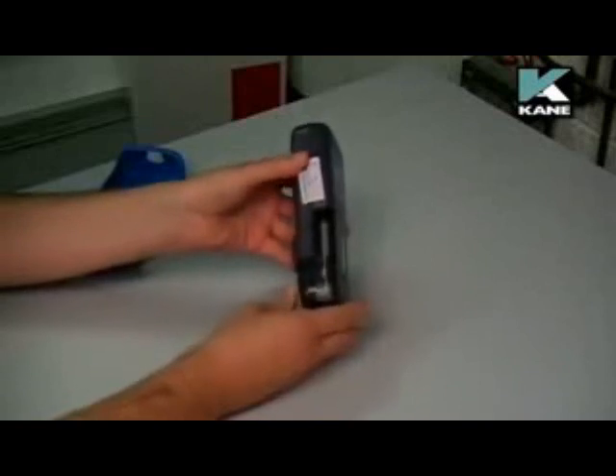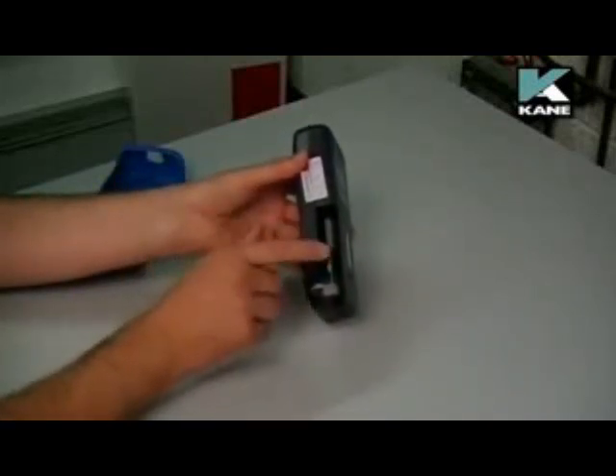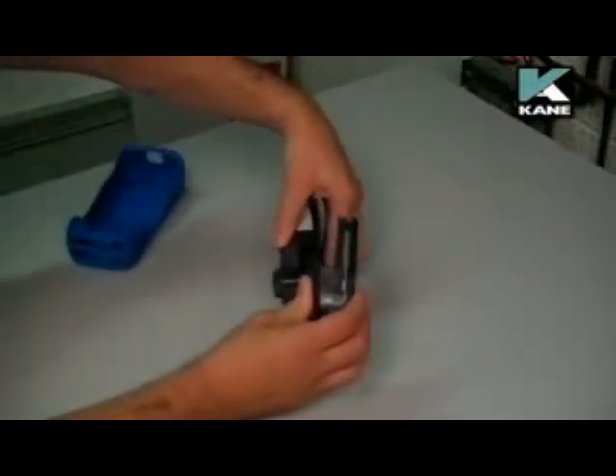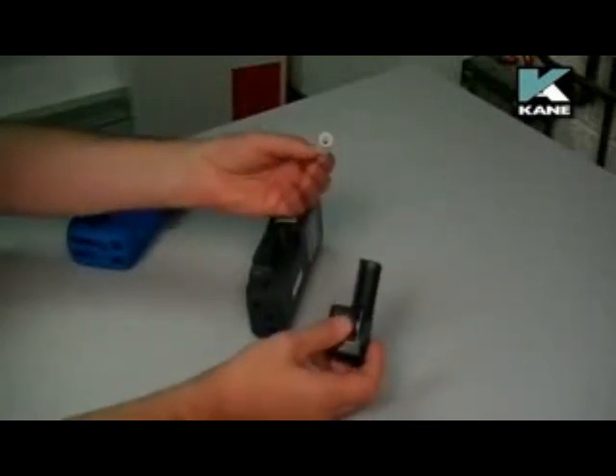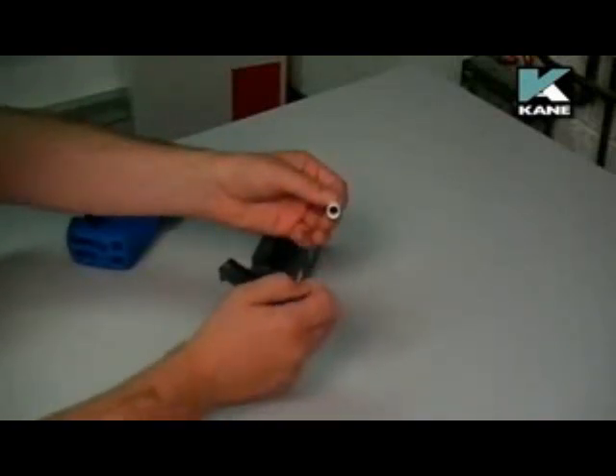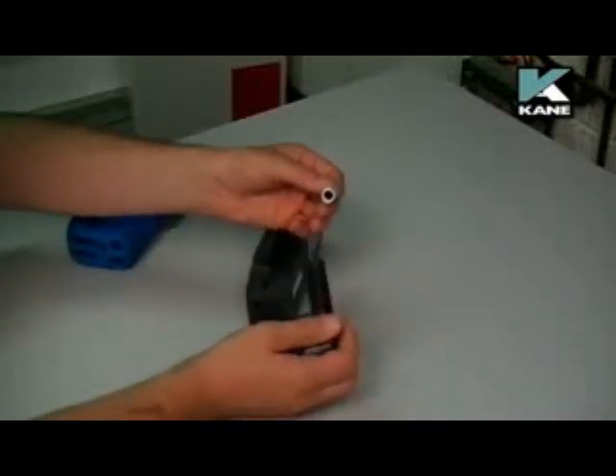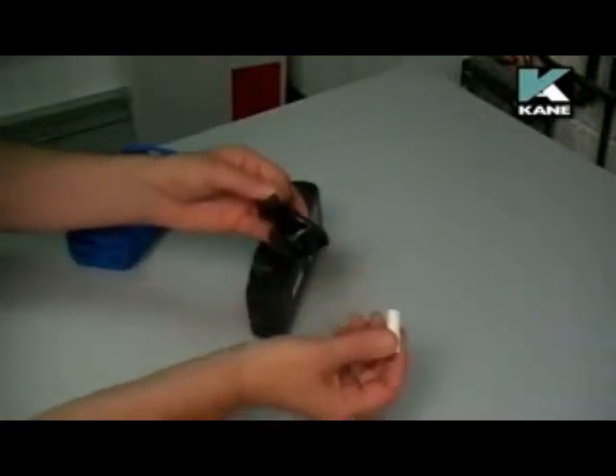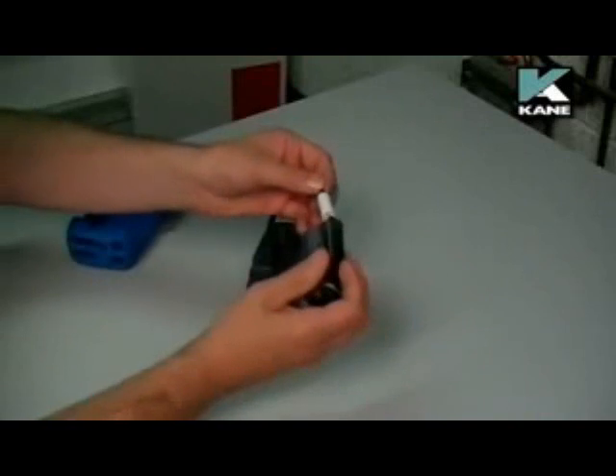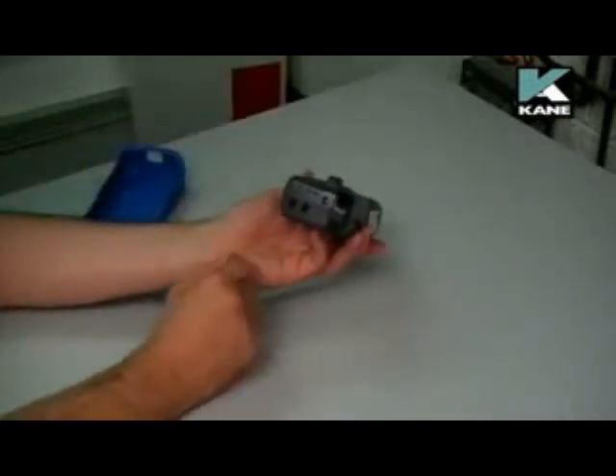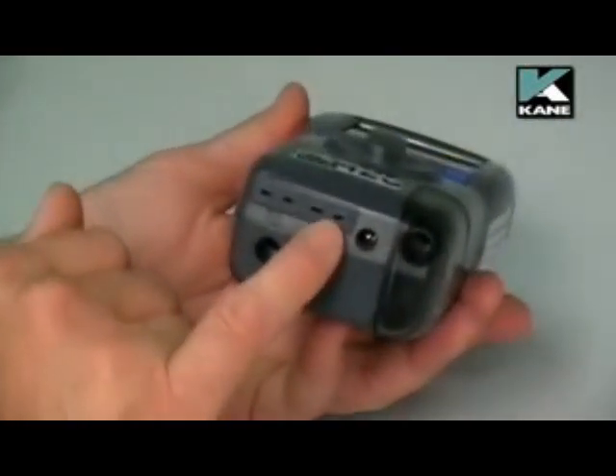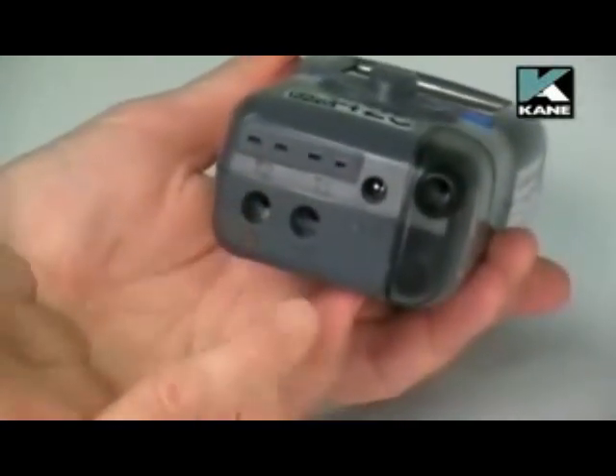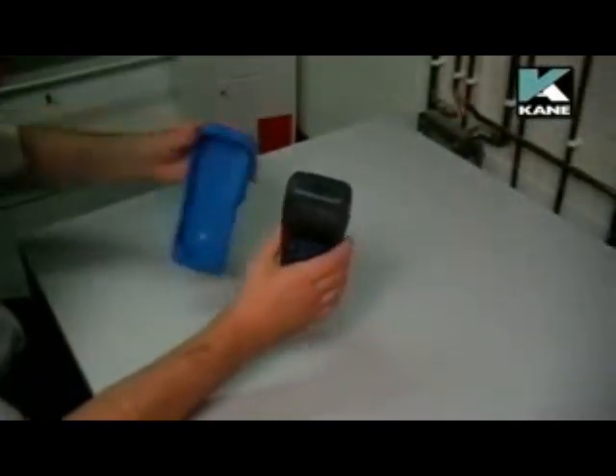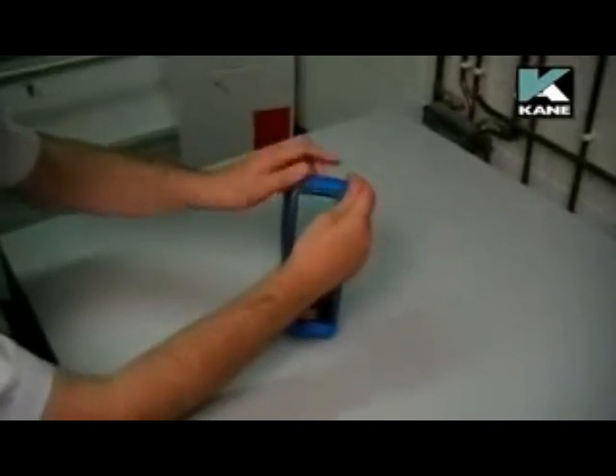Also on the side of the analyzer you can see the particle filter. To check this we need to remove this whole assembly and you can get to the filter. It's actually the middle of the filter that gets dirty first. So if that filter was blocked, dispose of this filter, replace it with a new filter and reassemble. Also, while we've got the rubber boot off, you can also see on the bottom of the instrument these connections are actually marked up as T1, T2, P1 and P2. Just replace the rubber boot, push it in at the bottom, pull it up at the top, and there you go.